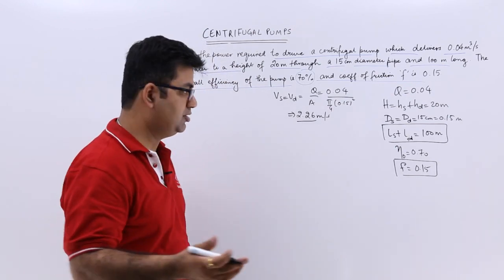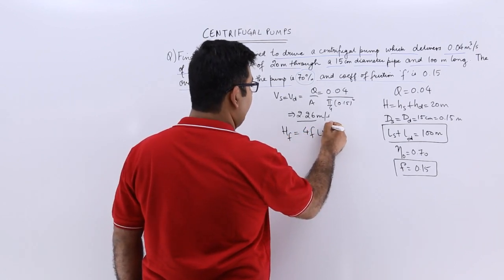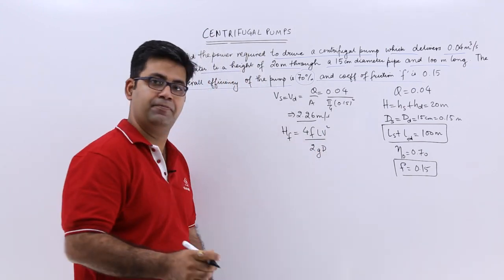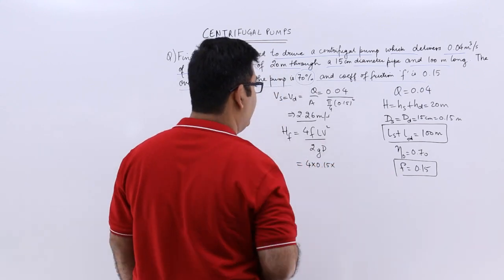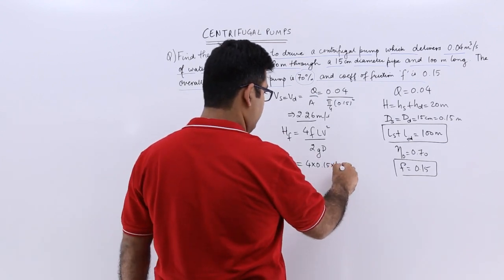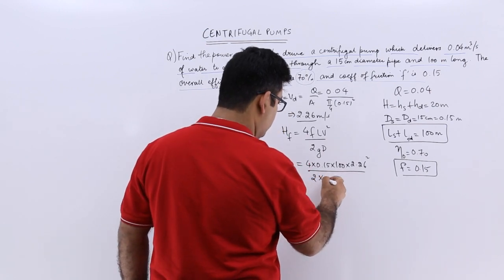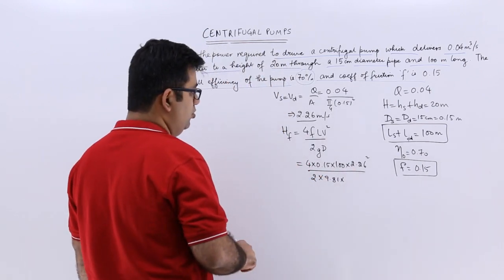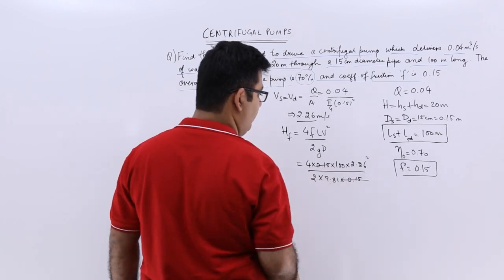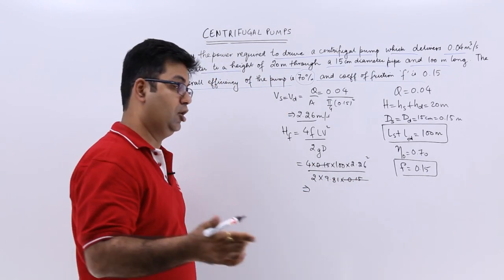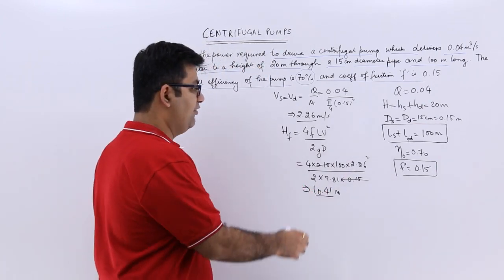The total friction loss H_F equals 4 × F × L × V² divided by (2 × g × D). Substituting the values: 4 × 0.15 × 100 × (2.26²) divided by (2 × 9.81 × 0.15). This gives a total friction head loss of 10.41 meters.